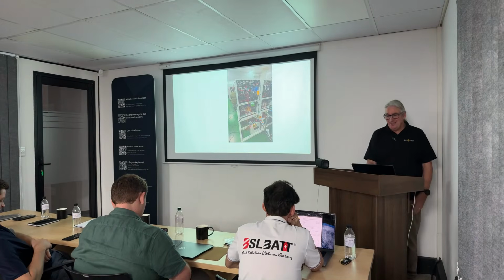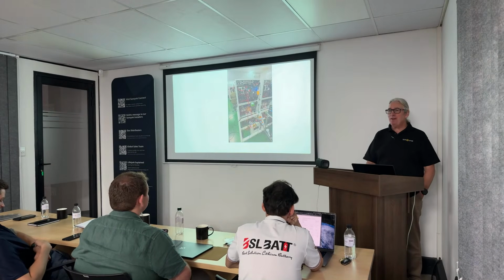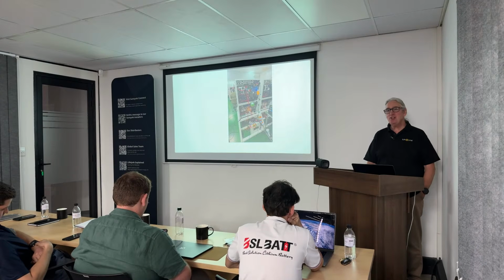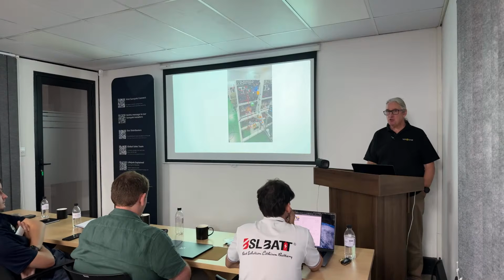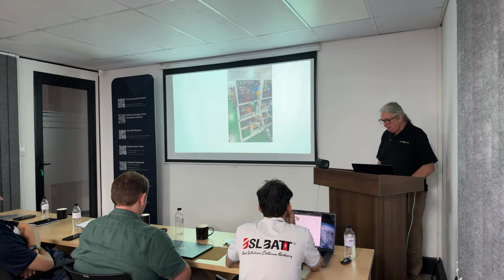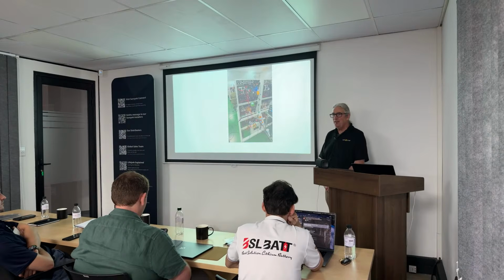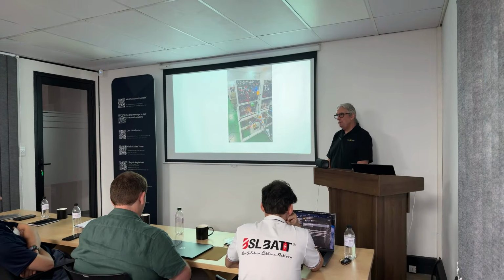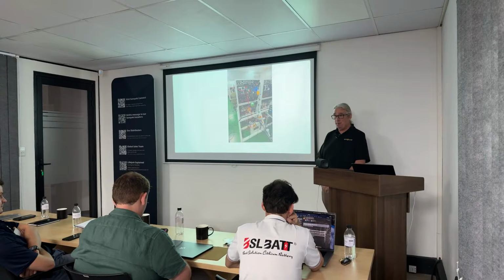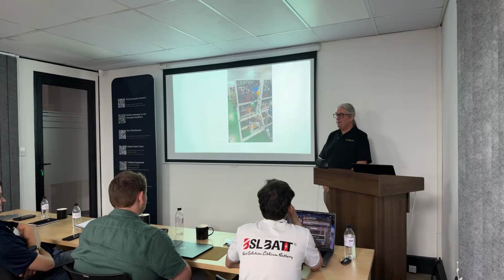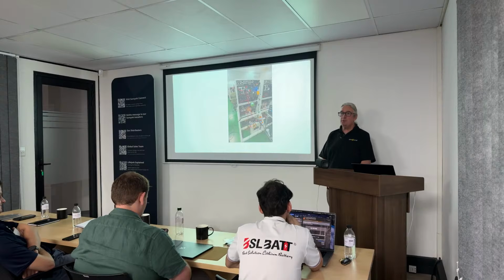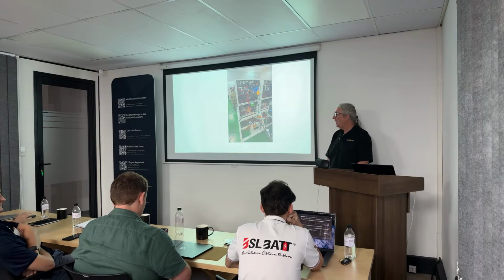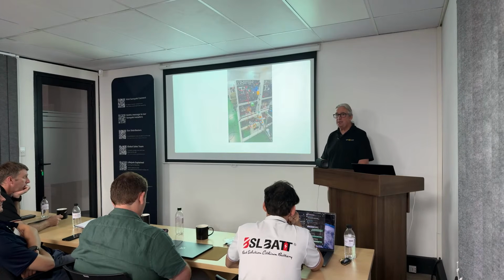I'm almost full - this is showing we've got a 125 kilowatt inverter coming, it's just in the R&D stage. This is a true hybrid, a true 125 kilowatt, not a string inverter with a DC stage. Some products coming on the market are actually string inverters with a DC stage added on, and they call it hybrid - I'm not going to mention names, but some famous companies do that. This is truly, absolutely true - it can export, it can import, it can do absolutely everything. It's got 10 MPPTs, 200 kilowatts of MPPT, all in one unit.